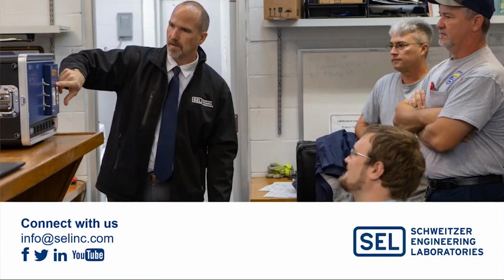Okay, I can answer those two questions. I'll answer the one about the data archiving function. The data archiving function is through DNP3 and not Modbus. Obviously Modbus is not an event-driven protocol, so it's polling heavy if you want to not miss information. We really like to use DNP3 for those applications.